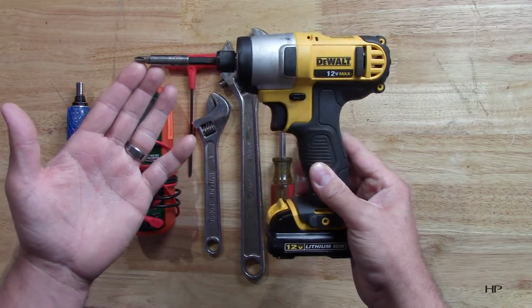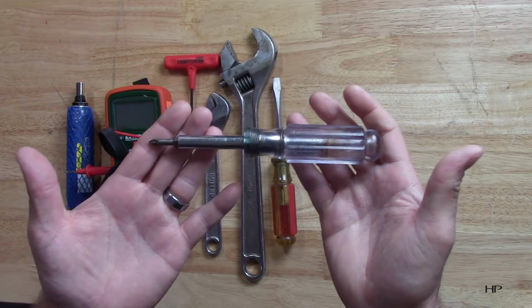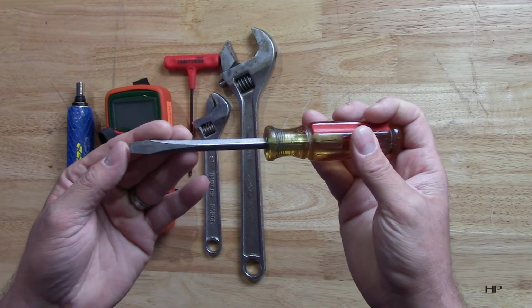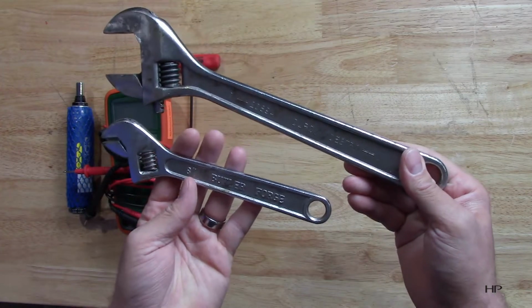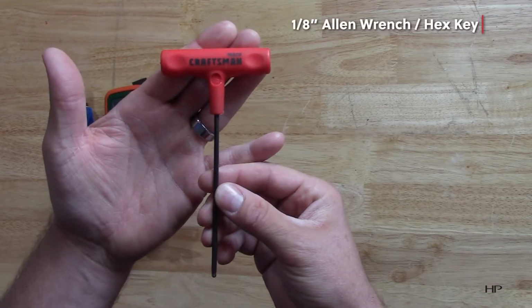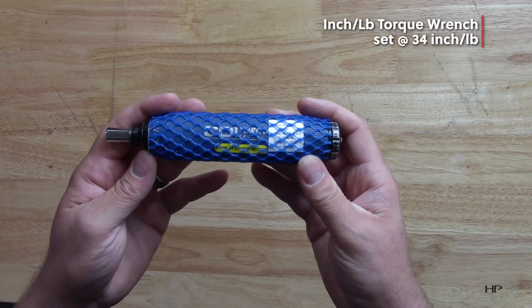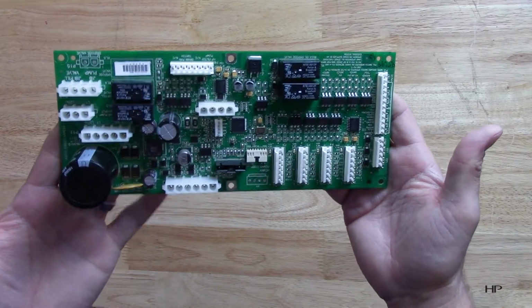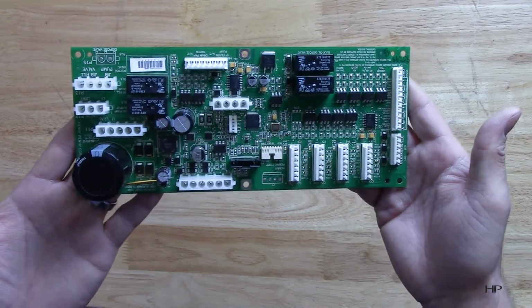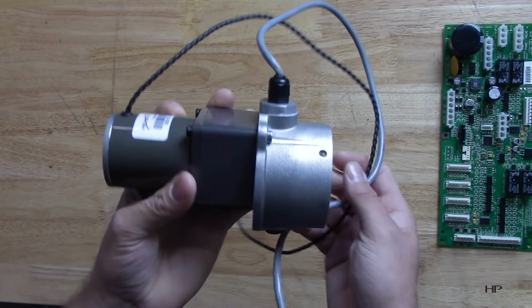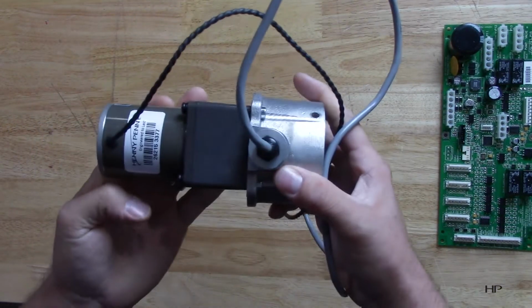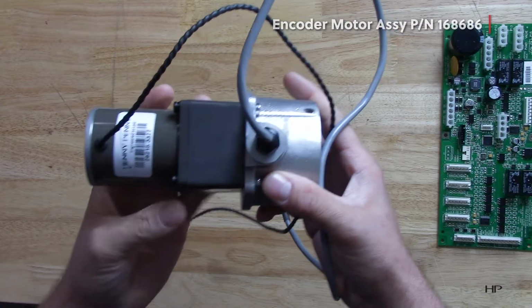I have a flashlight, powered screw gun, 6-in-1 screwdriver, a wider tipped flat bladed screwdriver, large and smaller adjustable wrenches, an 1/8 of an inch Allen wrench or hex key, multimeter, properly calibrated inch-pound torque wrench, blue Loctite. This brings us to some of the parts that we're going to need. The AIF board, part number 85698, encoder motor assembly. It's going to be a part number 168686.